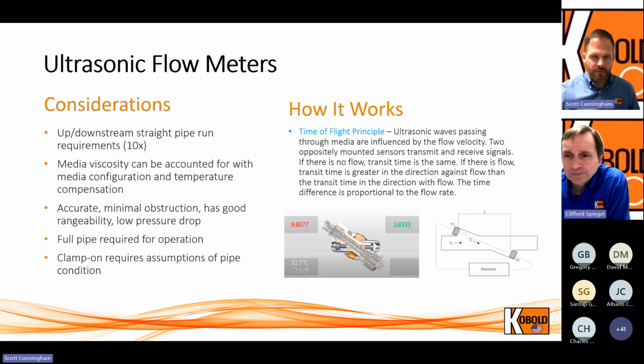Again, because there's no real obstruction in the path, you've got low pressure drop, and like we said, extremely high rangeability, meaning from the min and max, being able to measure pretty much the full operating range. As Cliff mentioned, like with all of our flow meters, you do need to have a full pipe. Cliff also mentioned the clamp-on technology: you're going to make some assumptions of that pipe condition. So if you give it a wall thickness and a material type, and you don't realize that there's scale built up on the inside of the pipe, your accuracy is probably going to be affected. Some of those assumptions and considerations you just need to keep in mind as you look to implement the technology. Anything else on that, Cliff, before I jump into how it works?